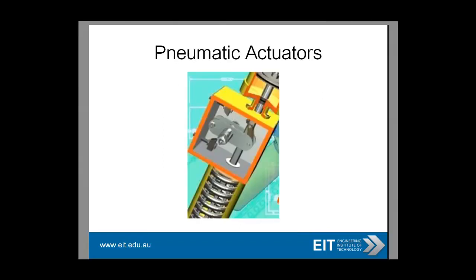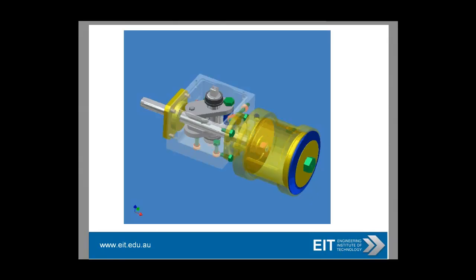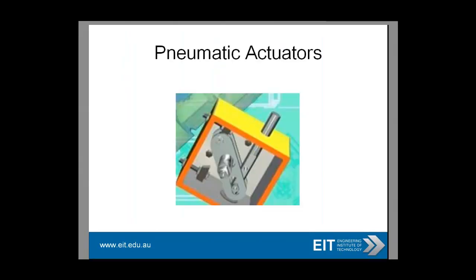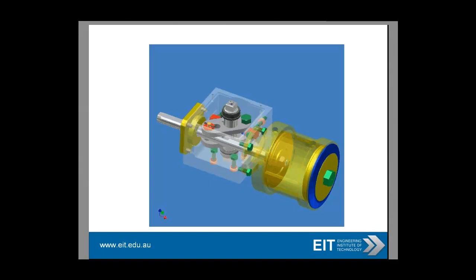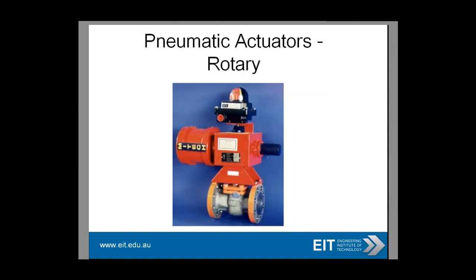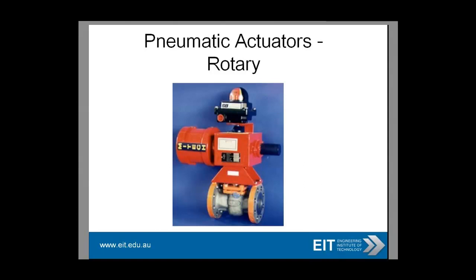There's also the double crank actuator, which provides high running torque, very low backlash, and is good for modulating control. Or you could go for the scotch yoke, which is good for on-off control and gives a very large torque — on-off being fully open or fully closed. Linear actuators aren't the only pneumatic actuators available. There's no reason why you can't go for a rotary type, usually operating a ball valve, butterfly valve, or rotary plug valve.